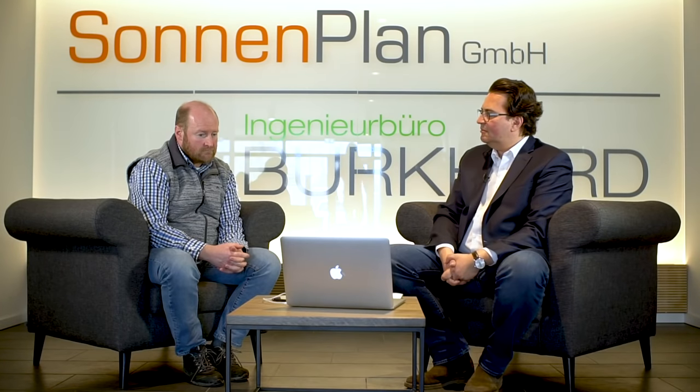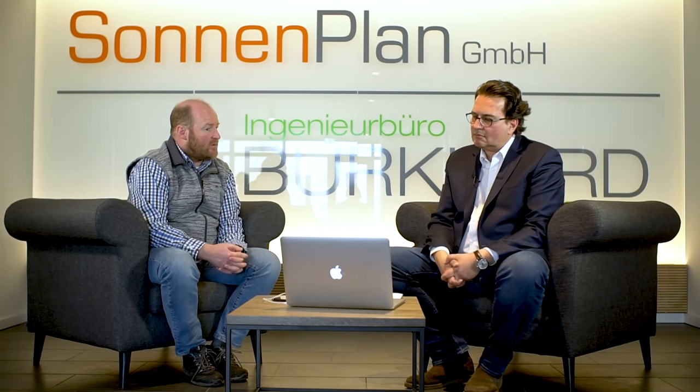Raspuino Tutorials schreibt: Es gibt Konvektorenheizkörper – sogenannte Tieftemperaturheizkörper mit Konvektoren-Lüftern – die ruhig mit 30 bis 40 Grad Vorlauf laufen. Das ist völlig korrekt, klar gibt es Tieftemperaturheizkörper. Wenn man ein Bestandshaus zum KfW 55 Effizienzhaus macht, wird die Heizlast viel geringer, und dann haben auch normale Heizkörper sehr niedrige Vorlauftemperaturen. Das ist eine völlig richtige Geschichte, die man auf keinen Fall verheimlichen will.